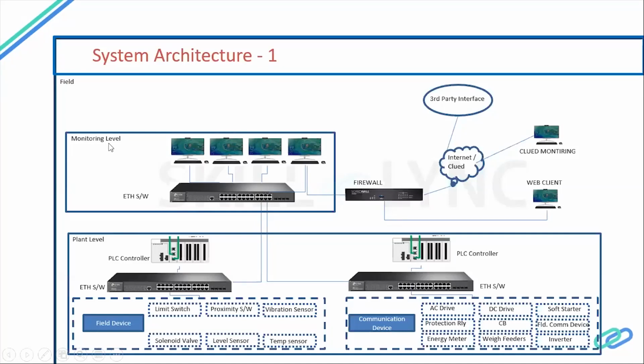After that is your monitoring level. All the controllers are connected with your monitoring level stations. This is basically for the plant control stations. In this plant control station, one may be a server, or one a client, or one an OPC client, and one a storage server. As per our requirement we create the architecture, and we define this architecture at detail engineering time only.